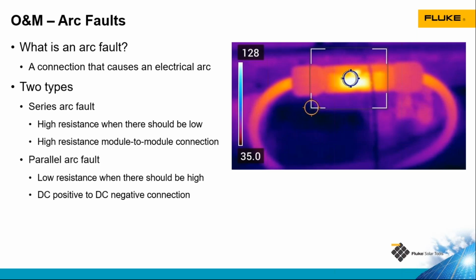The other type of arc fault is a parallel arc fault, and this is the opposite of a series arc fault. This is a low resistance connection when I want a high resistance connection. An example here would be DC positive and negative conductors making contact. So maybe those two wires got pinched together, and now it's arcing between the positive and the negative.